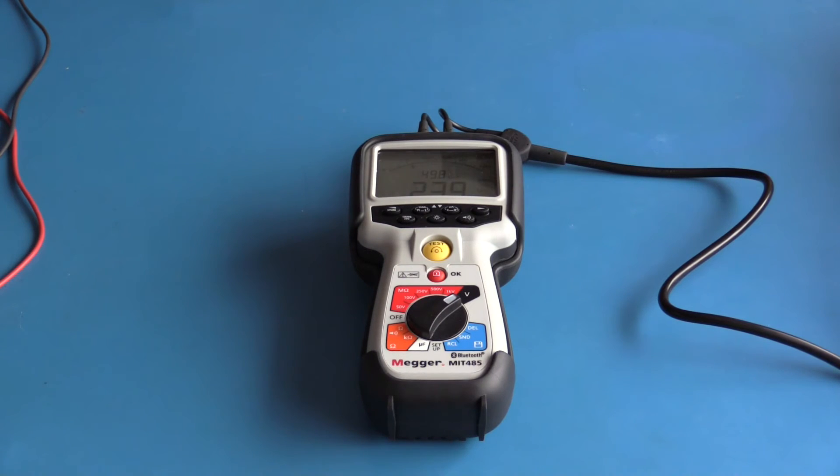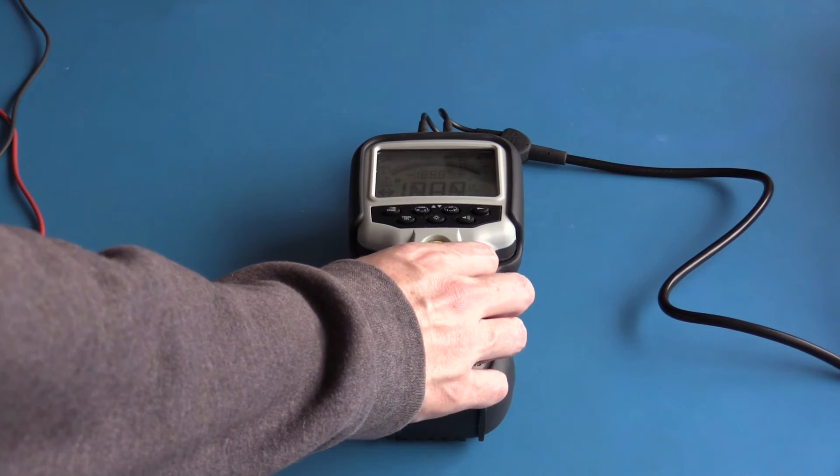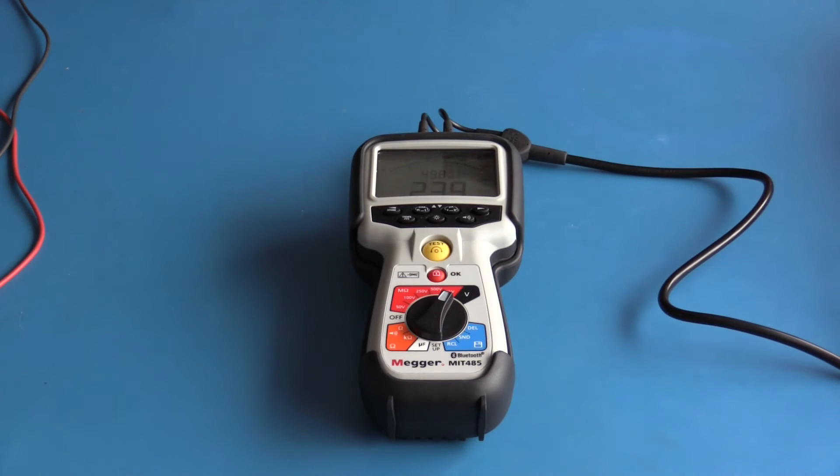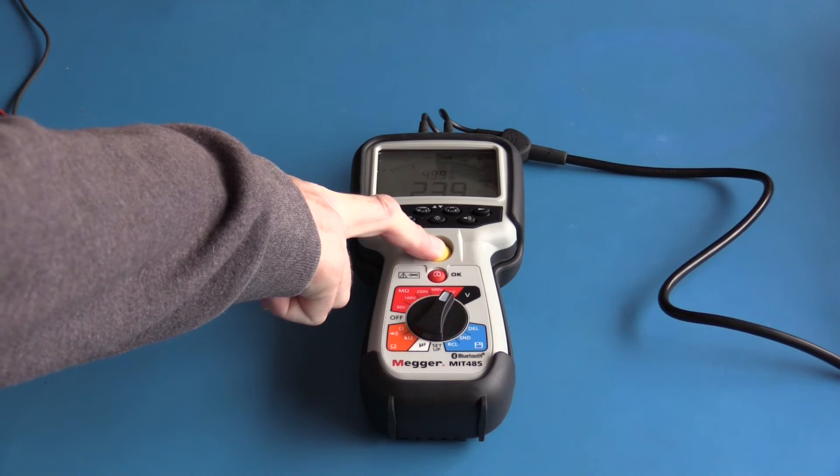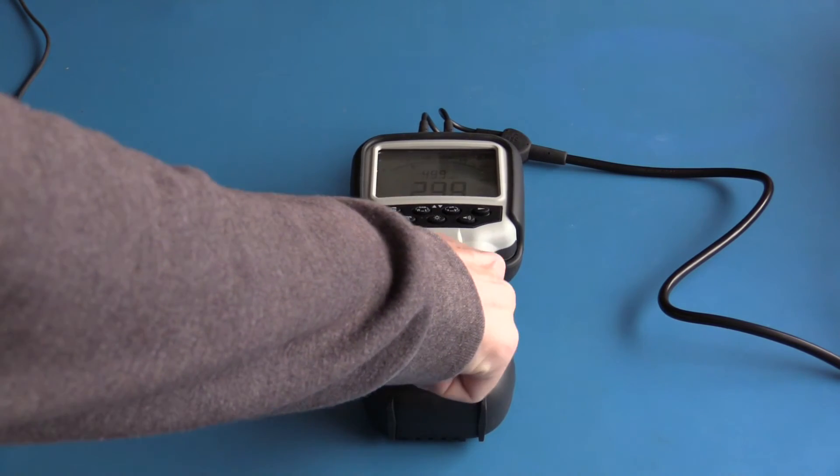With the meter on this live circuit, if I switch to another function, the meter will beep and alert me that this circuit is live. It also enables test lockout. As you could see, I was not able to perform the insulation resistance test.